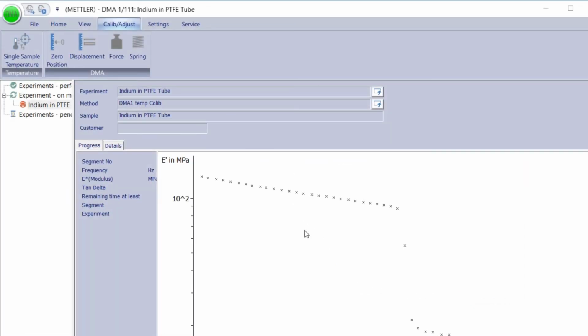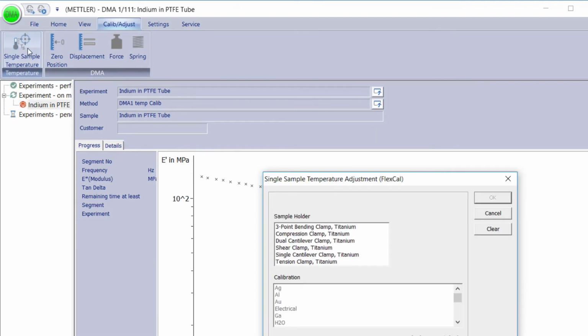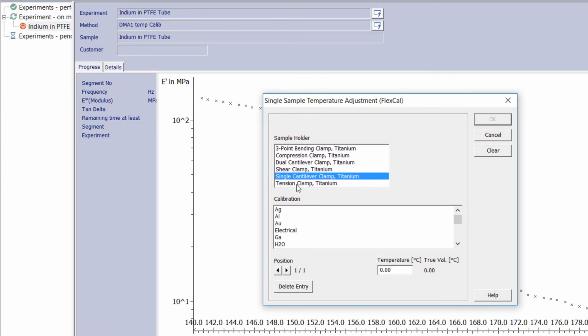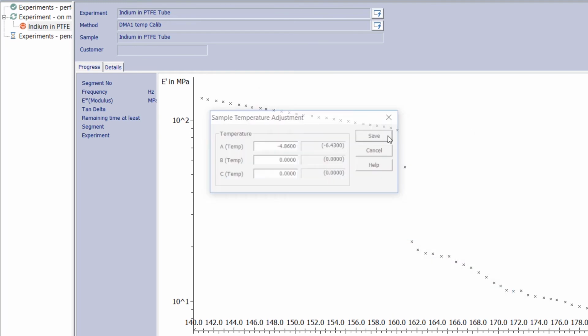Temperature calibration can be performed for each individual clamp under Calibration Adjustment, Single Sample Temperature Adjustment in the module window. Enter the evaluated onset melting temperature for indium in the box next to the true value. Simply click Save to perform the temperature adjustment.